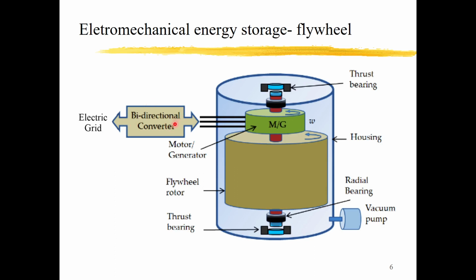And when we need to store electricity, the power comes into the flywheel system, and this is the MG set. MG set means motor and generator set. So the electricity here makes it behave like a motor, and the motor provides torque to the rotor and speeds it up. The rotational speed increases, so the kinetic energy increases. The whole system is enclosed in a housing. The rotation speed is very high, and there will be air friction, called windage loss.